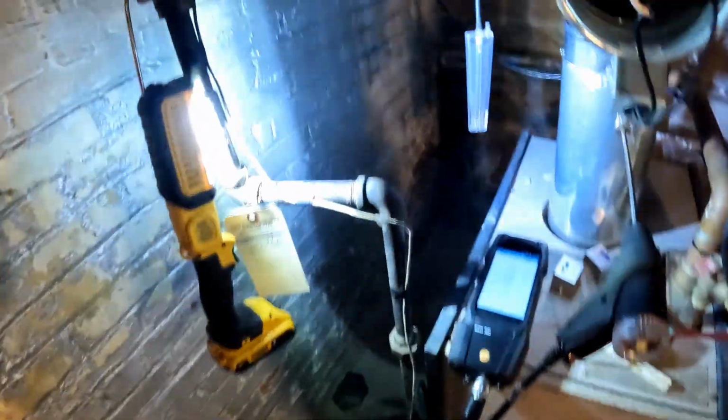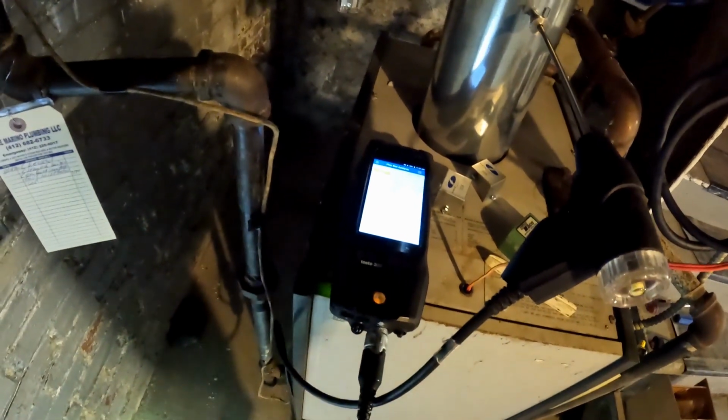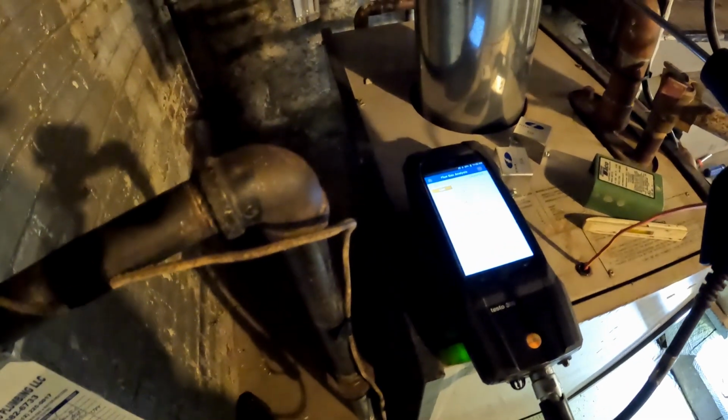Okay, after conducting a test for 10 minutes or so of the boiler running without the inducer, I was barely maintaining a 0.1. Excuse me, not 0.1 parts per million, 0.1 draft pressure. And the carbon monoxide was slightly rising and lowering. Now this is stable at 6 parts per million. On initial light up, we didn't go up anywhere near the 400 or 500 range. So the inducer has to stay.